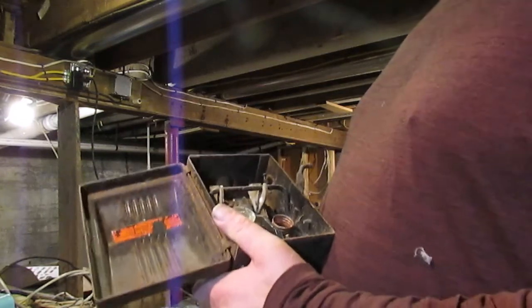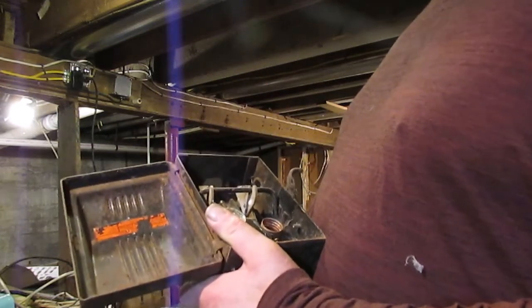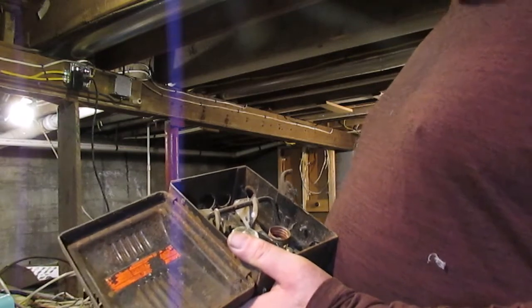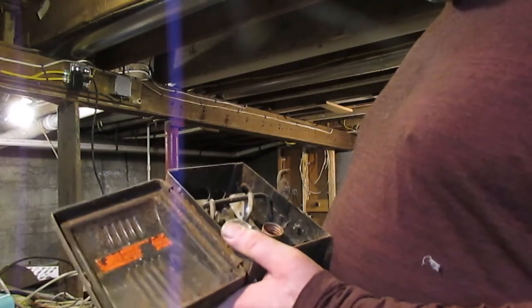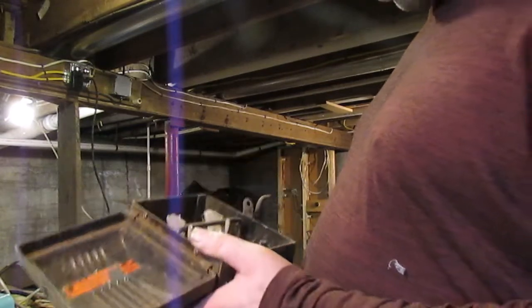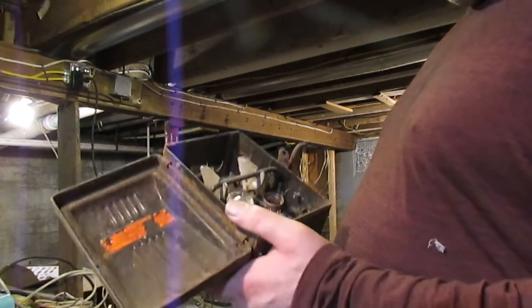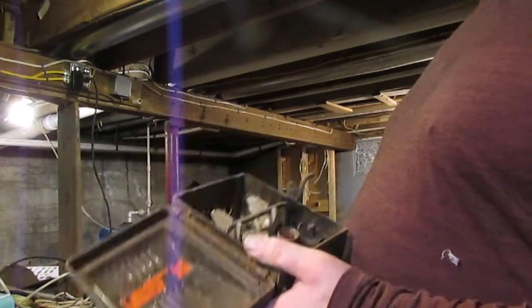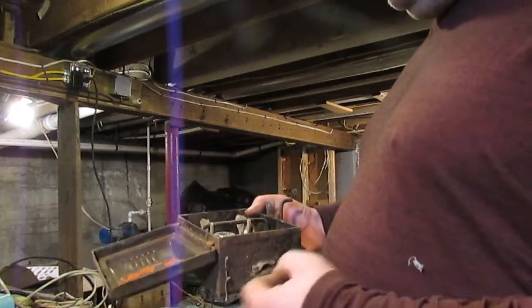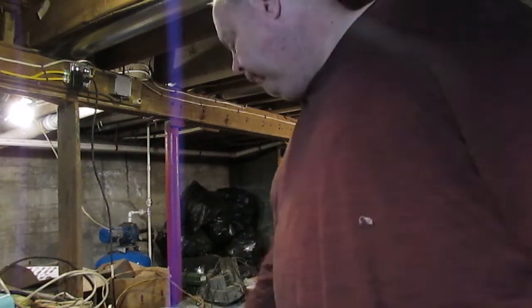Most likely you could use this on an outdoor piece of equipment like a conveyor or something like that that had an electric motor on it. You could use this for a disconnect switch for an electric motor. As far as using this in a house, I probably wouldn't use this on anything inside of a house nowadays. Insurance companies won't allow it anyway, so that's pretty much it.